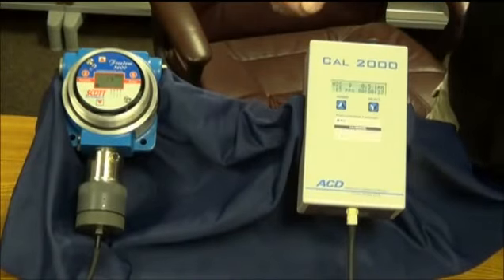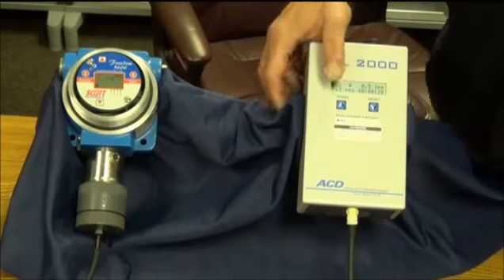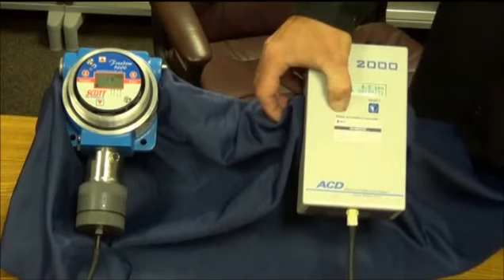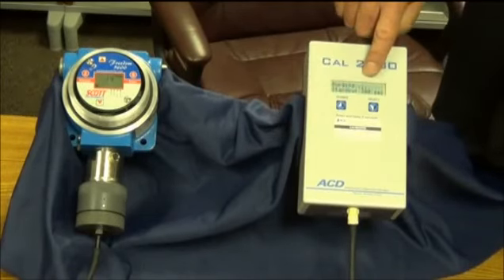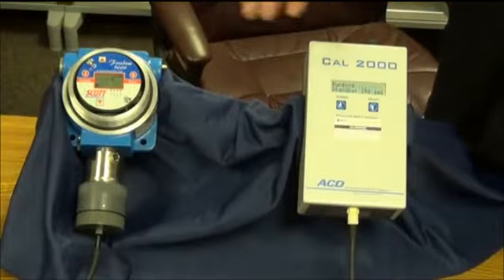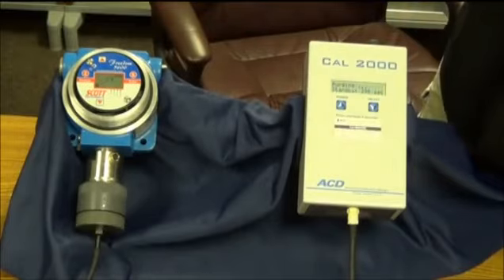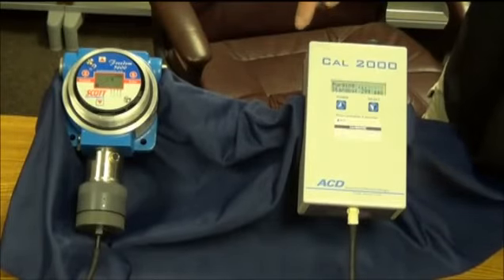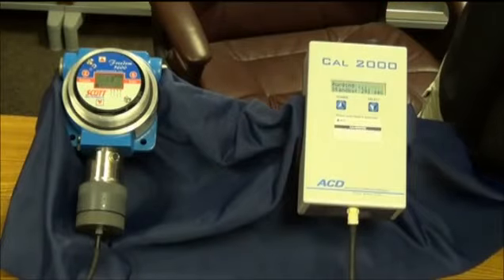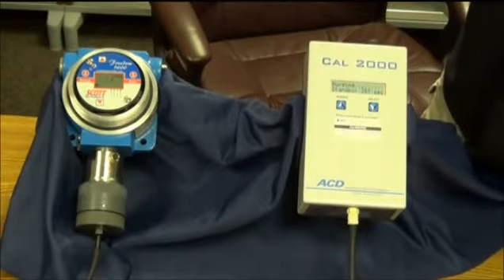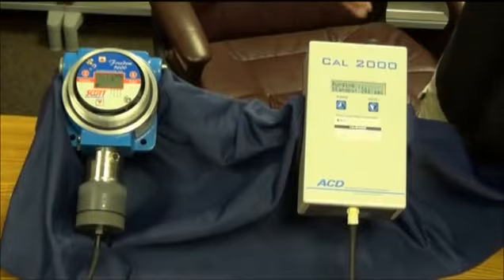Alright, once you've finished your calibration with the Cal 2000, to power the unit off, you press and hold the power button for 3 seconds. It says purging, and it purges for 5 minutes just to get all the corrosive gas out of everything. And the instrument will remember the last setting you had. So once this power's off, if I turn it back on, it'll come back to 15 parts per million. That way, if you calibrate one particular sensor all the time, you don't have to reset it each time you go through.